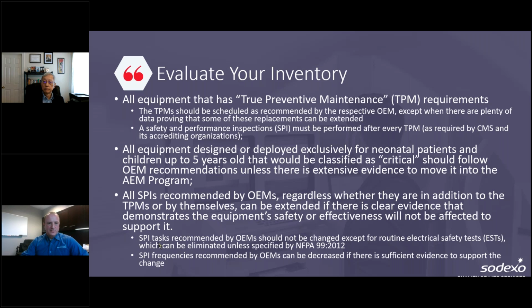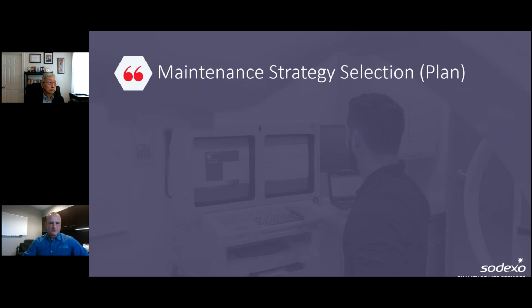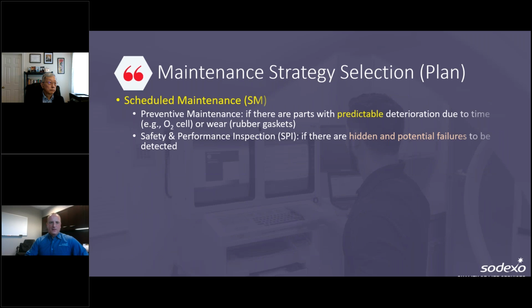Right, so all SPIs recommended by OEMs, regardless of whether they are in addition to true preventive maintenance or otherwise, can be extended if there's clear evidence. Again, NFPA 99/2012, if your hospital has adopted that, you can exclude the electrical safety testing.